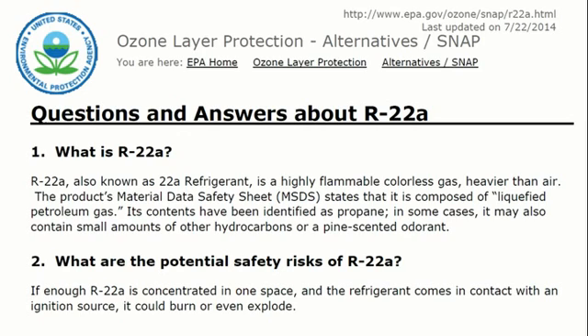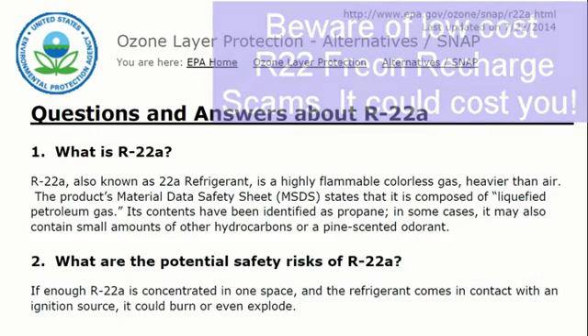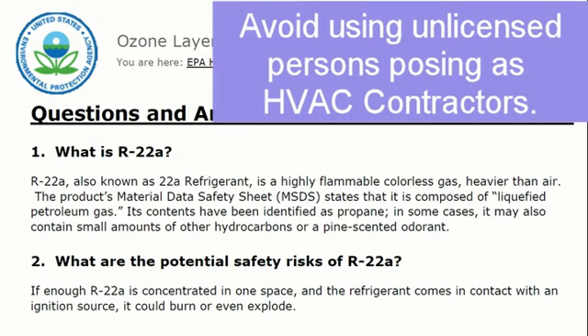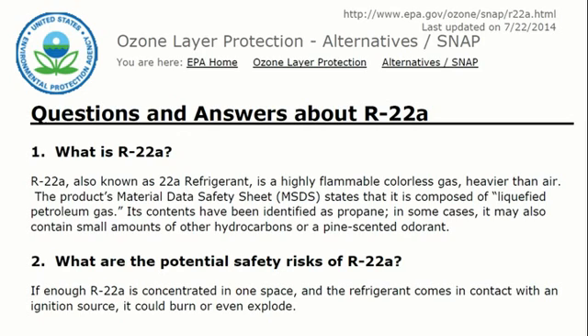Questions and answers about R22a. R22a is a highly flammable, colorless gas, heavier than air. The product's material data safety sheet states it is composed of liquefied petroleum gas; its contents have been identified as propane. In some cases it may also contain small amounts of other hydrocarbons or a pine-scented odorant. If enough R22a is concentrated in one space and comes in contact with an ignition source, it could burn or even explode. This R22a has been passed off as a do-it-yourself refrigerant, but there is no silver bullet here.